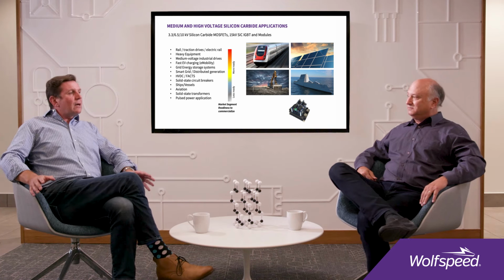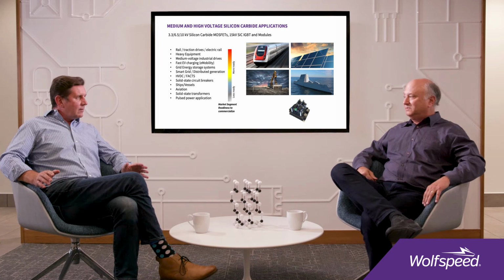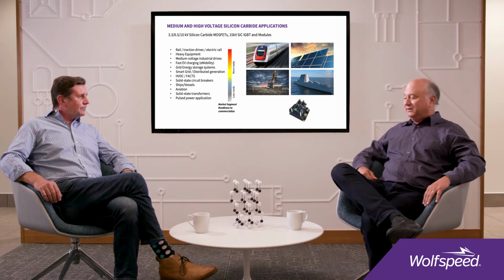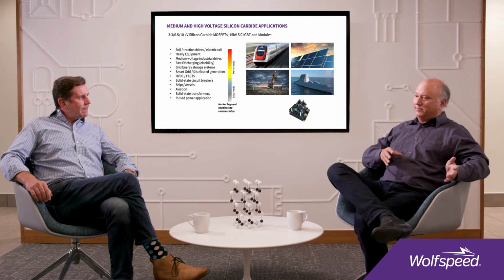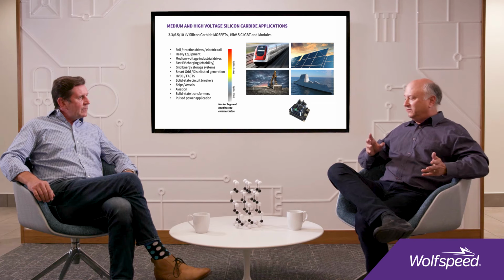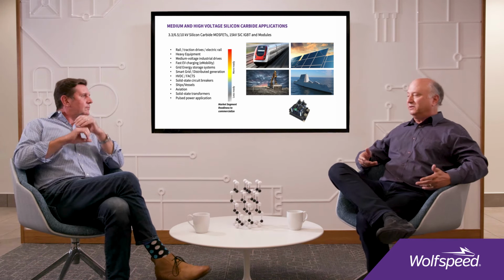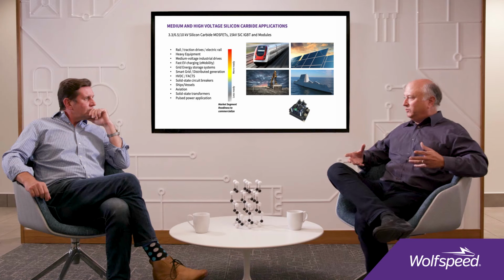Okay, so this really does enable a brand new space. It really does, and we've talked a lot about 650 volt up to 1700 volt. The savings with silicon carbide are undeniable - it brings a lot of benefit, but as you go higher in voltage, that benefit gets even stronger. So whereas we might cut the losses at 1200 volts by say 70%, at 3.3 kilovolts it's 1/10th the loss.